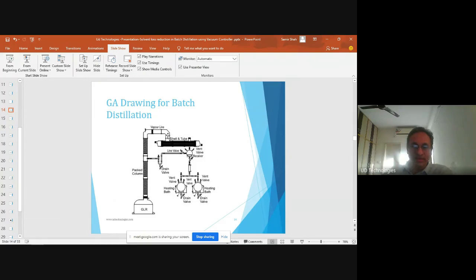What happens is that in a horizontal condenser there will be dropwise condensation. When the vapor reaches the tube's outer surface, it gets condensed and immediately drops, the condensate passes to this level, and the uncondensed solvent vapor travels up to the end of the condenser. Because of dropwise condensation there will be no subcooling of the vapor and minimal subcooling of the condensate. So the outlet temperature of the vapor will be much higher, right?